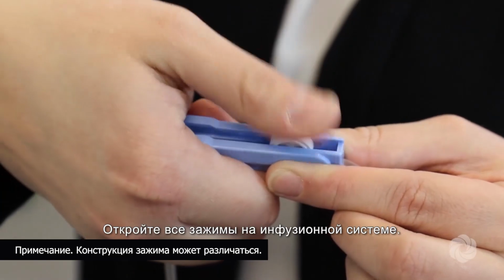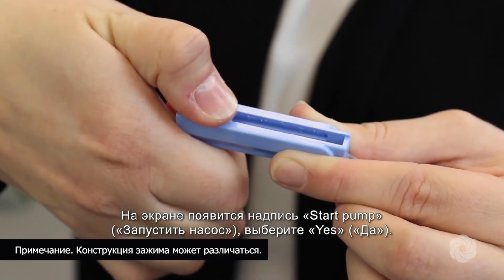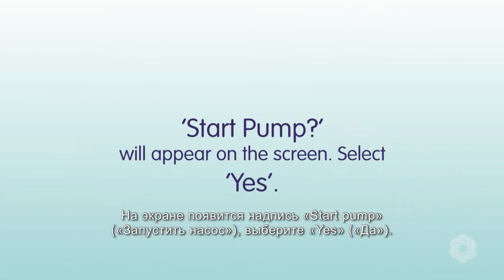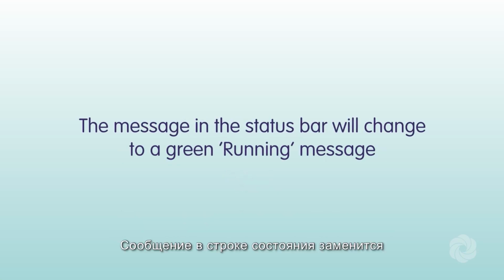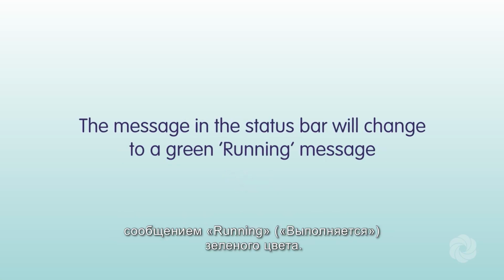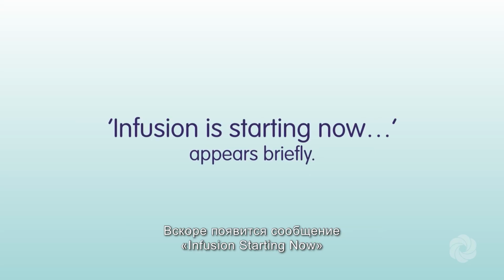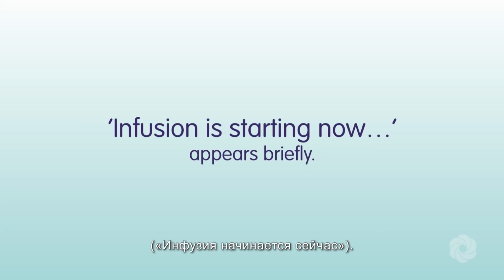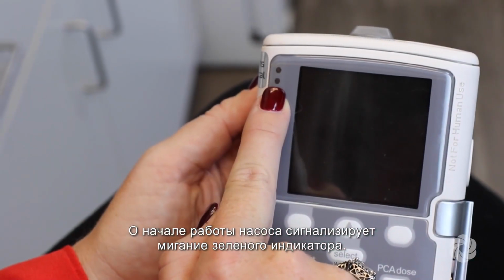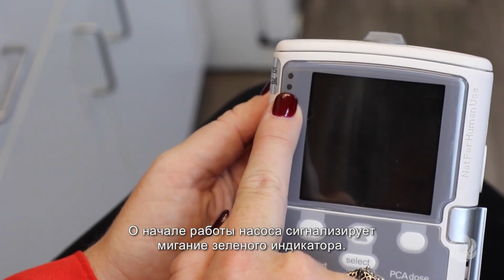Open all clamps on the IV tubing. Start pump will appear on the screen. Select Yes. The message in the status bar will change to a green running message. An infusion starting now appears briefly. You will know the pump is running when the green light is blinking.